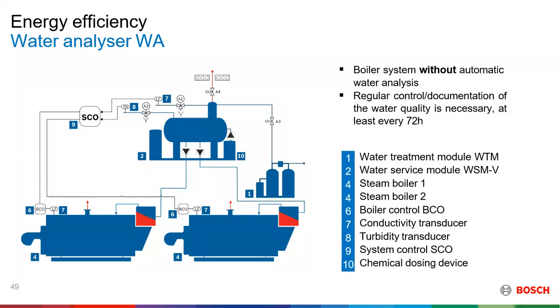So in this setup, you have a system where you have a water analysis module with a system control. So the SCO with the system control to control the two boilers below. So you have probes in the feed water tank measuring conductivity and turbidity of the water.